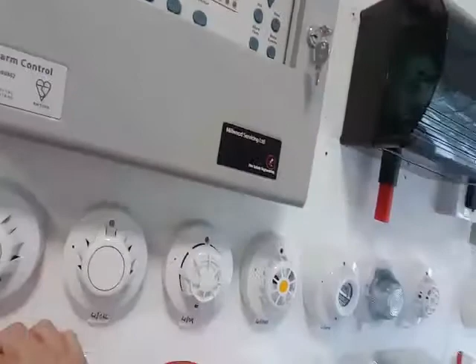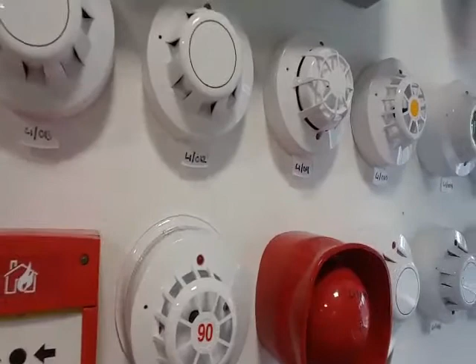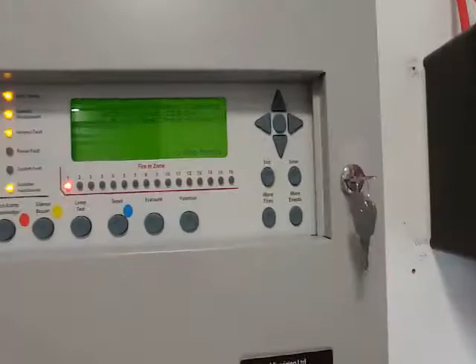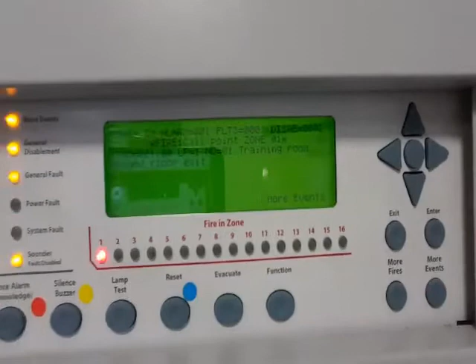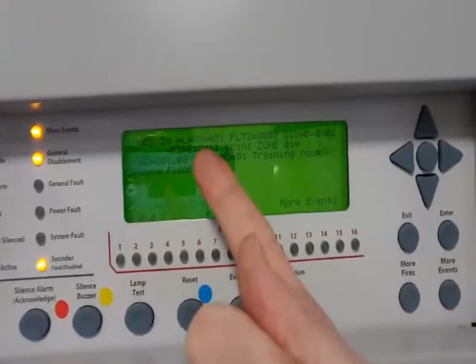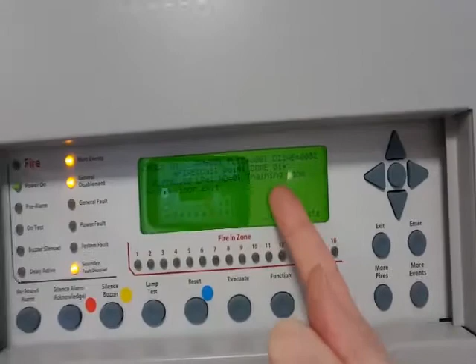So here's an example. If we set off this manual call point here by pressing this button, the fire alarm's going to go off. We've turned off the sounders, otherwise it will blow the speaker. But what you can see, hopefully, is that the information has come up with exact detail: ground floor exit, call point, zone 1, address 1, loop 1, training room, and then lots of other detail here.